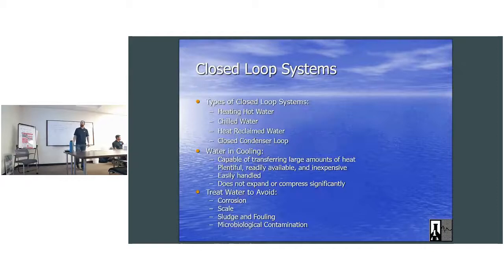On that pot feeder, you're using the supply pressure off the discharge of the pump to circulate through the pot feeder. What's nice about those, like Dan said, is you valve it off, you drain the water out, you fill it with chemical, put the top back on it, and turn the valves on. So you're not introducing air, and more importantly, you're not adding volume to the loop. You're not adding an extra 5 gallons. You're taking out 5 gallons of untreated water and adding 5 gallons of treatment, and then letting it circulate.